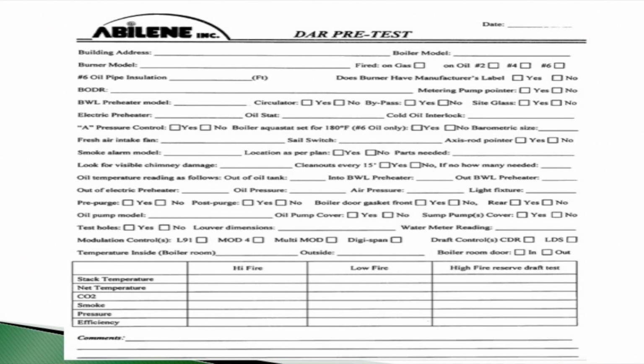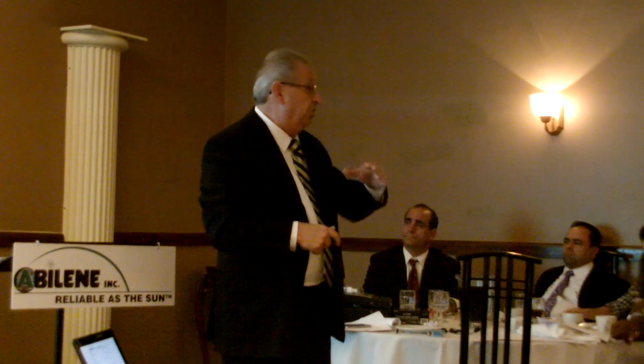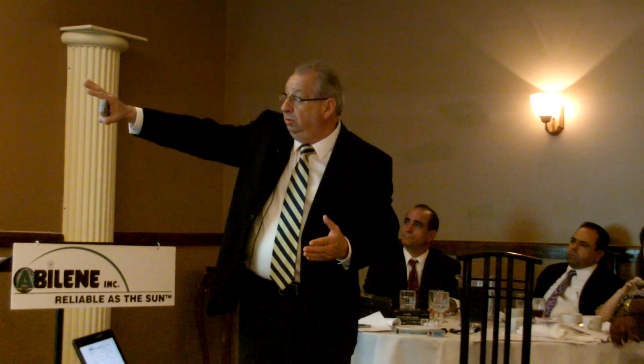Few little points to help the service department to pass the job. And when you go through this list, you can have this list. If you want, we can just give it to you, and you can look through it quickly. And you can write down what fan you're putting in, what boiler, what burner. BODR stands for burner oil delivery rate, or boiler oil delivery rate, which means metering pump and the pin number. So you put that in, and then you go through all of these little checks.